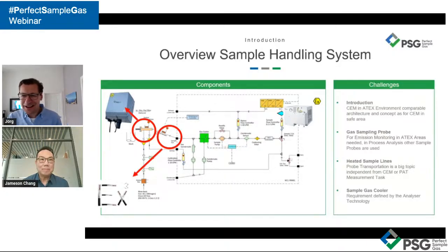Yeah, that's right. And then what is the final task of a gas cooler at the end, Jimson? Just briefly, in this overview of the sample handling system. In the gas cooler, it is not simply a dryer by itself. We have to consider a few critical factors, why there are different types of exchangers, and why, at the end of the day, be it response time or losses, we want to say one thing. A good gas cooler does only one thing: it provides you a constant sample outlet dew point. This is a good gas cooler.